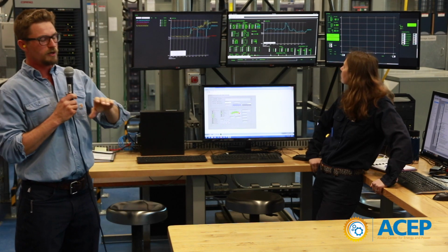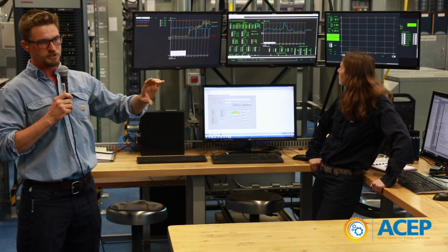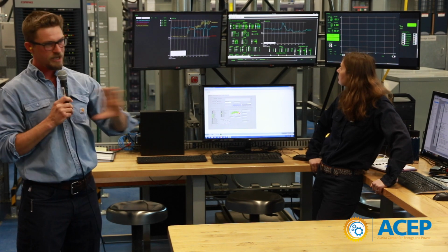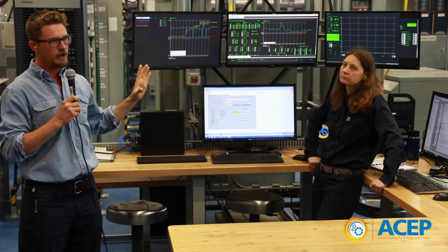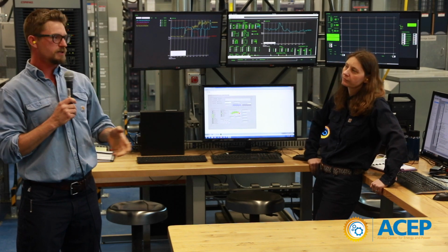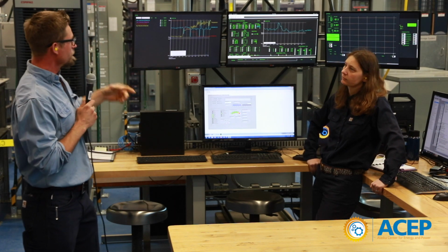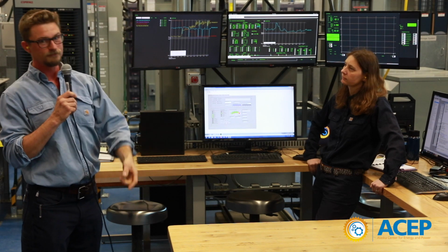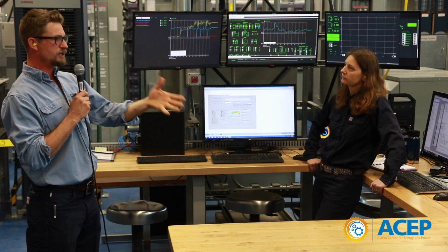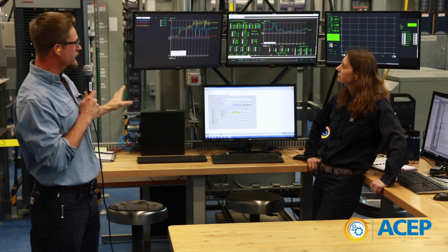We're spending a lot more time with the low loading on our diesel generator. We keep the same generator running. We can't turn the generator off, right? We can't turn the generator off for the same reasons. Because if the wind power drops down to 0, we need to have that generator there. So we keep the same size generator running.